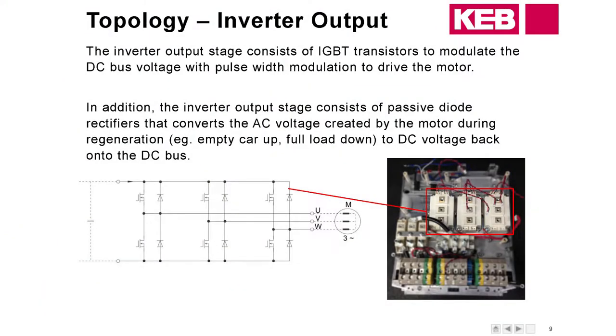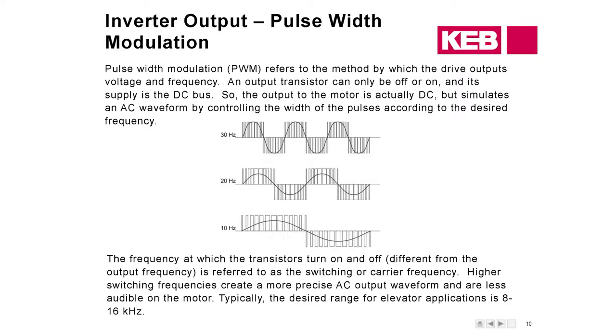Moving on to the output of the drive — this is where the IGBTs are. In this example you can see three separate modules, one for each phase. The units in front of you have them on one single module, just a variation in hardware layout. The IGBTs pulse on and off very quickly — that quick pulsing is referred to as PWM, pulse width modulation. That uses a carrier frequency, or switching frequency, which is different from the frequency output to the motor. So if you're troubleshooting and you see you're outputting 30 Hz to the motor, that is different from the carrier frequency.